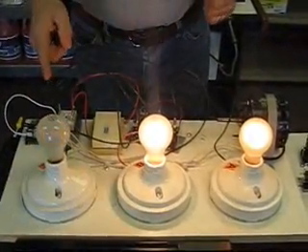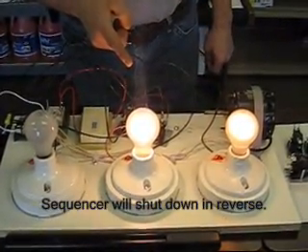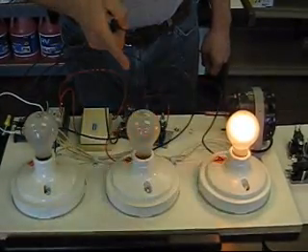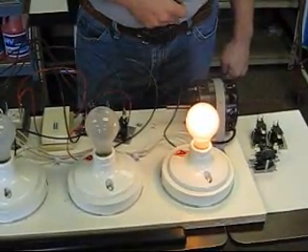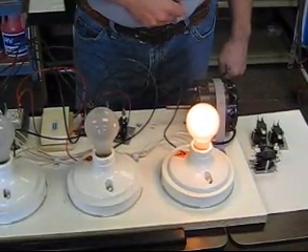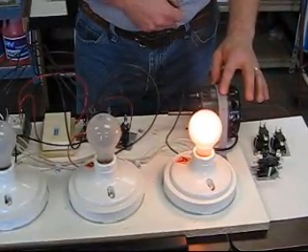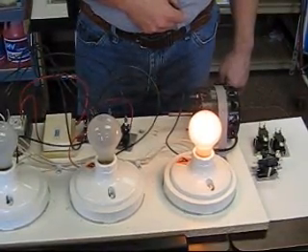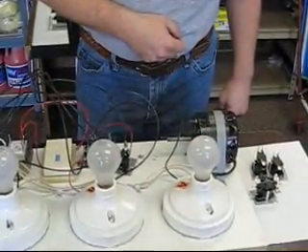In a few seconds, this will come off. And then this next element will shut down. And then in a moment, the last element in the blower motor will shut off. And they're off. And that's how a sequencer runs.